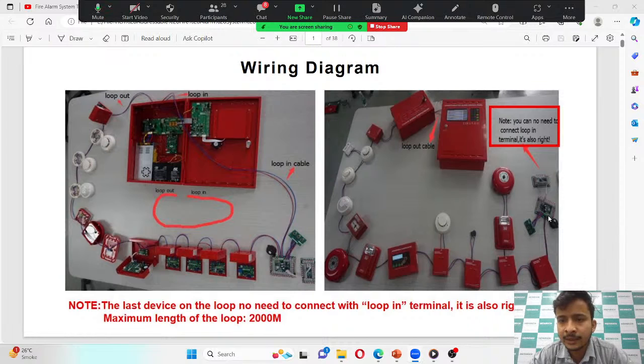The second option is that you take one two core cable from the panel, and then loop all the devices one to another, one to another, like this. The last end of the wire is terminated as an end of line. You need to connect one end of line resistor there, and it will be the last of the loop. The maximum length of the cable from the panel to the last device is up to 2000 meters, almost 2 kilometers.